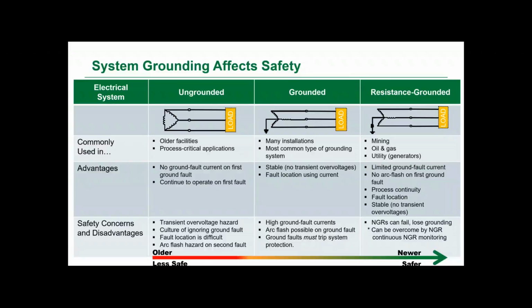So there is a risk of transient overvoltage. There's also some difficulty in locating the ground fault. And there's also a real possibility that ground faults may be ignored for some time, depending on what type of ground fault indication system is available, which can lead to some system-wide insulation degradation. And that itself can mean future, more frequent faults and more escalation into phase-to-phase faults.